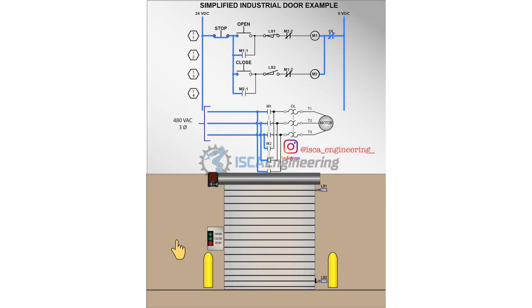The example we have provided is of a simplified industrial garage door. The garage door is provided with limit switches in order to prevent the motor from running continuously and thus damaging the door. These limit switches have been wired as normally closed, meaning that whenever the limit switch is not actuated, it provides power to the motor when their respective button is pressed. So let's take a look at the circuit.